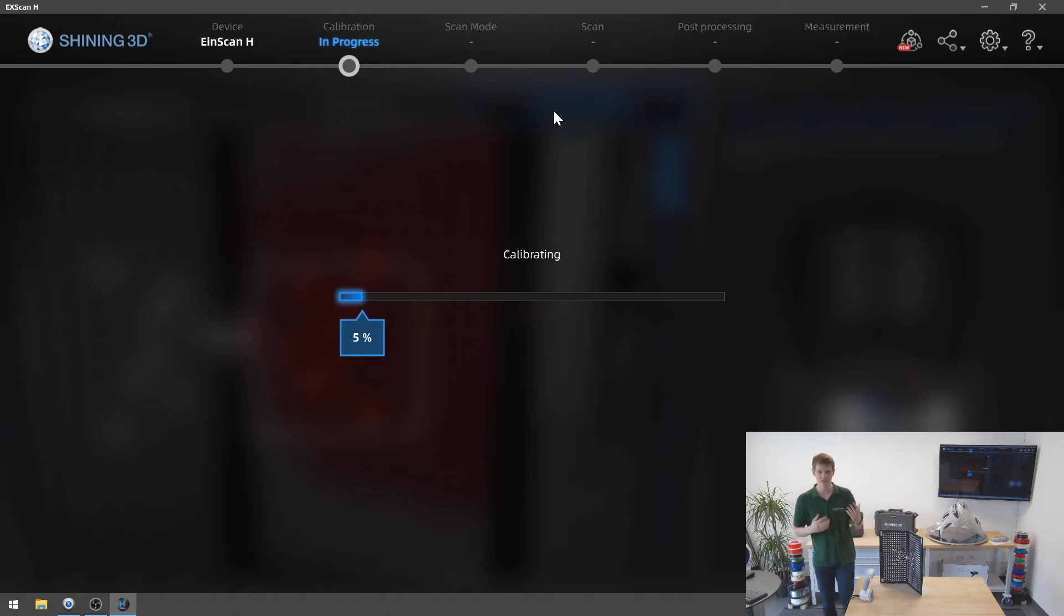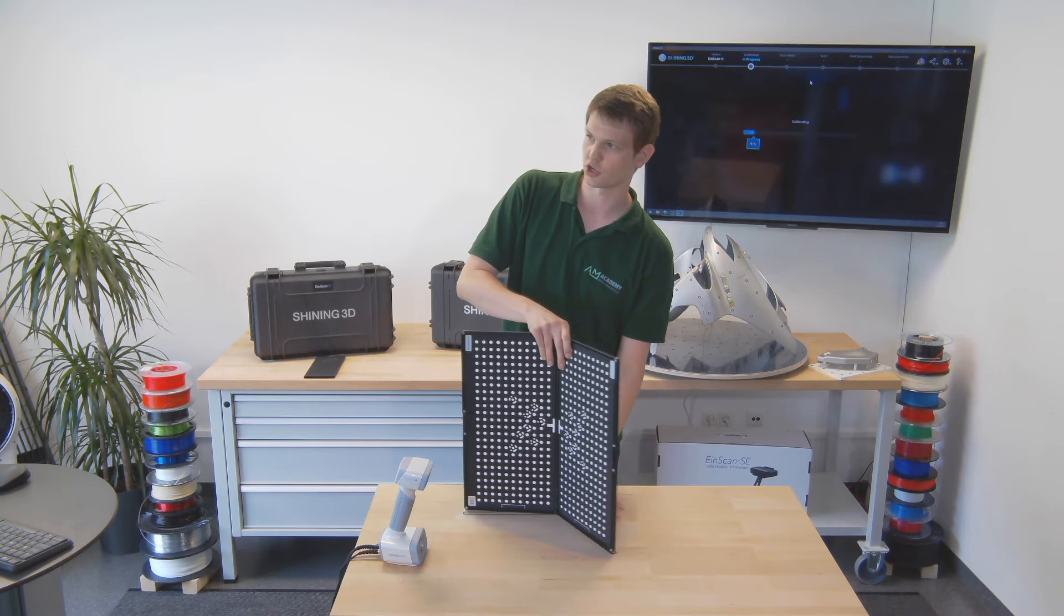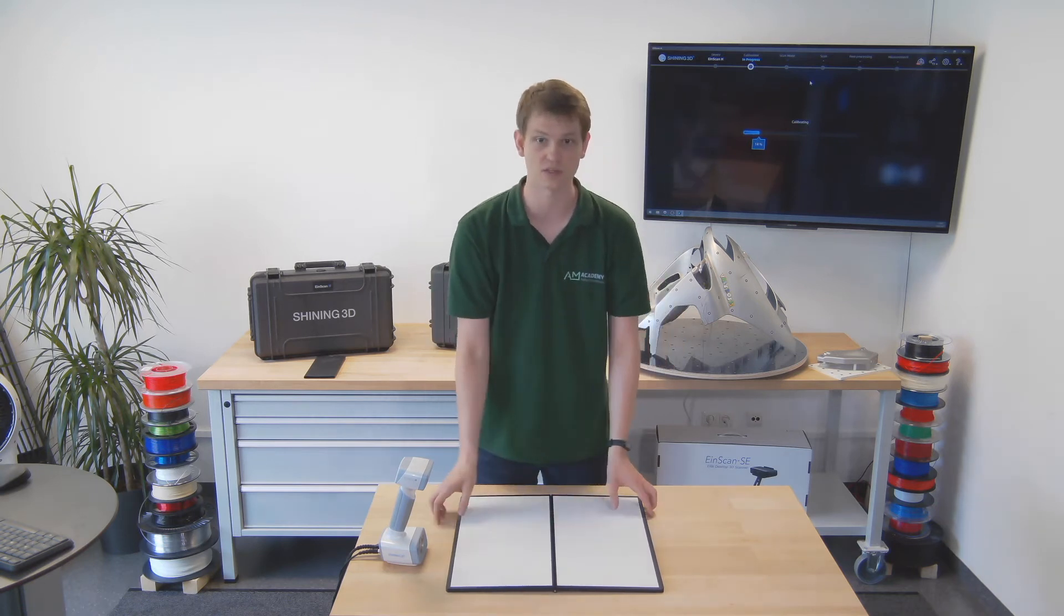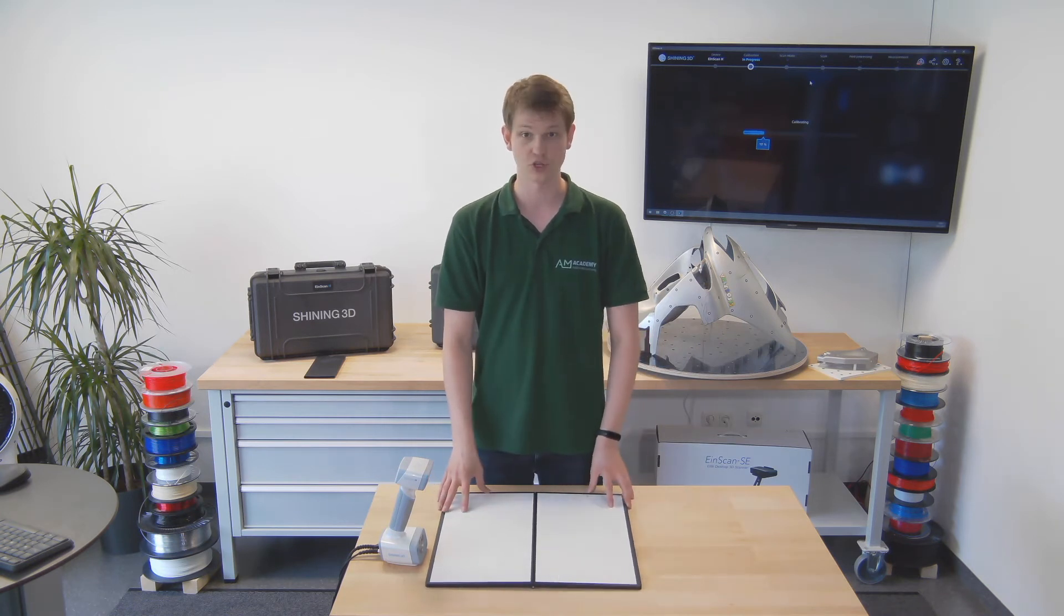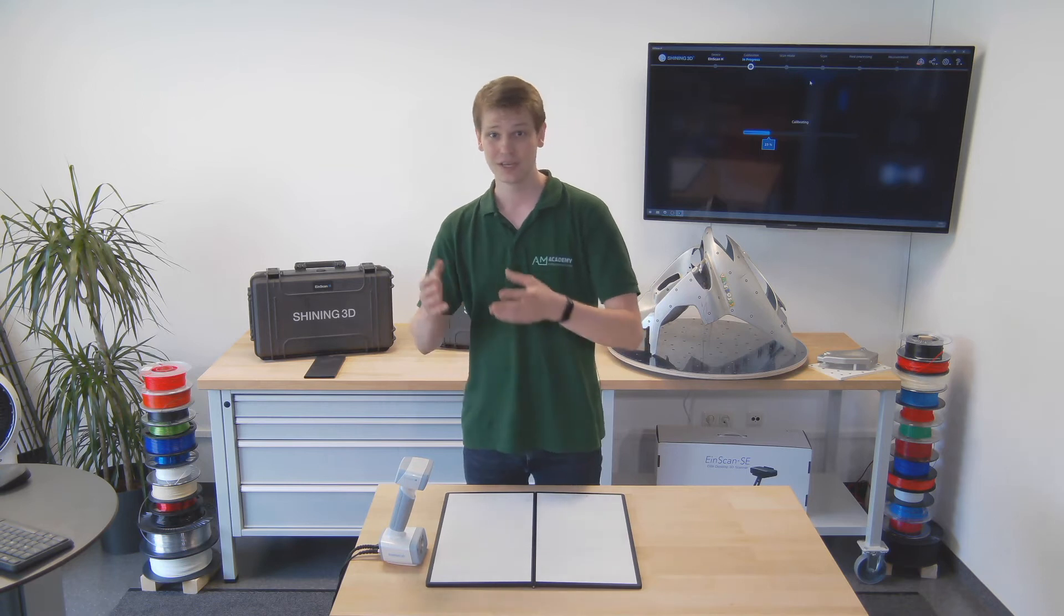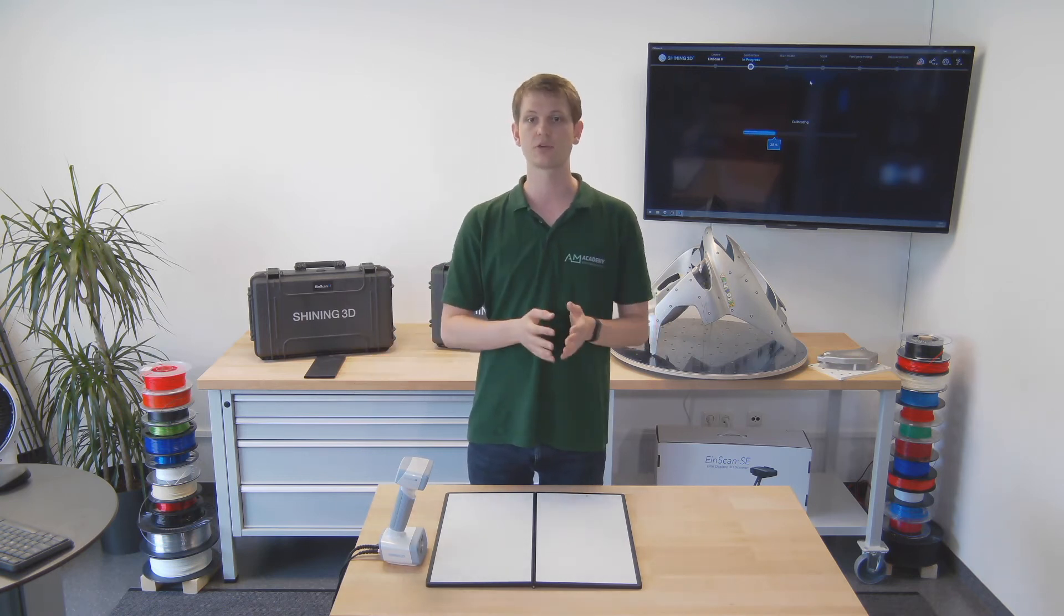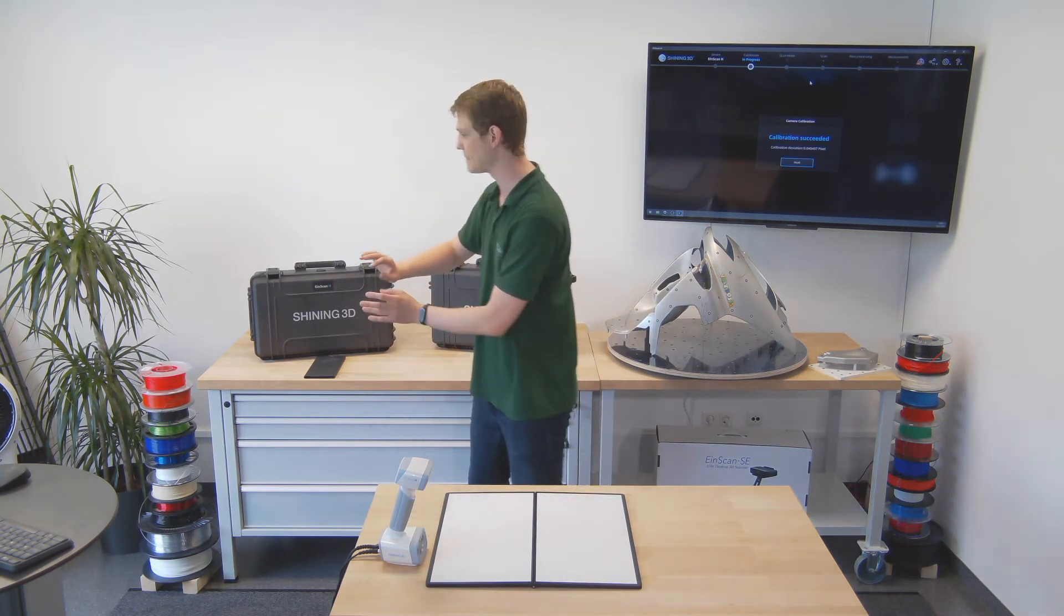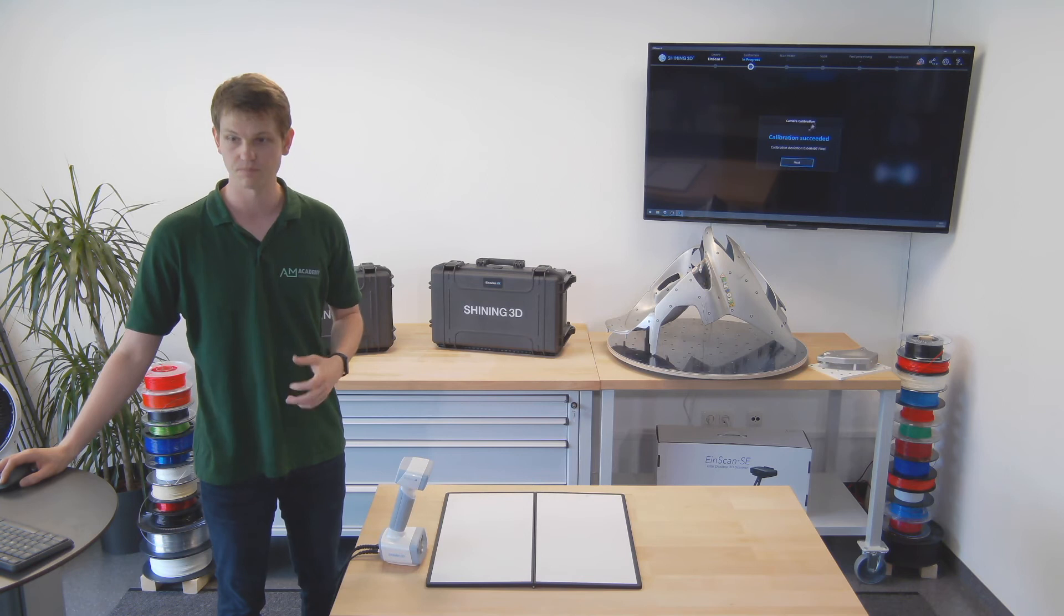Now the scanner software is calibrating. The next step will be a white balance calibration, so you flip the board on its back so the white side is facing outward. It's important to not damage this board because if it's too damaged, your calibration will be bad—it'll have errors, not work at all maybe, or your accuracy will simply not be as high. So make sure you take good care of this board.